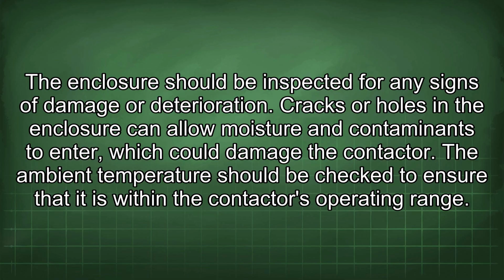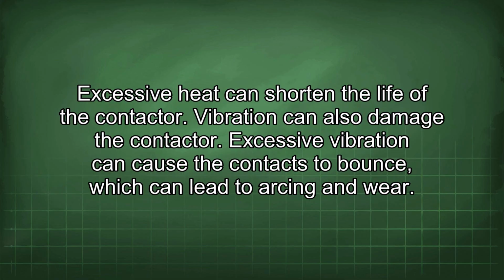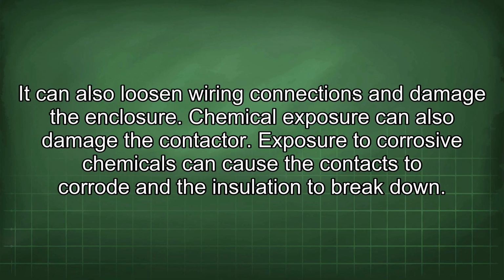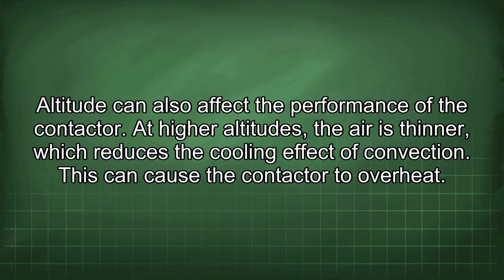The ambient temperature should be checked to ensure that it is within the contactor's operating range. Excessive heat can shorten the life of the contactor. Vibration can also damage the contactor. Excessive vibration can cause the contacts to bounce, which can lead to arcing and wear. It can also loosen wiring connections and damage the enclosure. Chemical exposure can also damage the contactor. Exposure to corrosive chemicals can cause the contacts to corrode and the insulation to break down. Altitude can also affect the performance of the contactor. At higher altitudes, the air is thinner, which reduces the cooling effect of convection. This can cause the contactor to overheat.